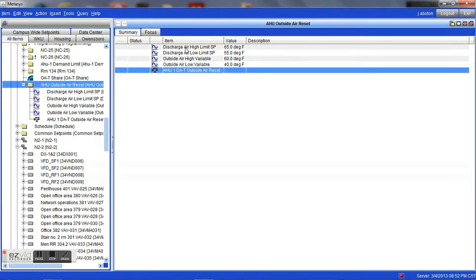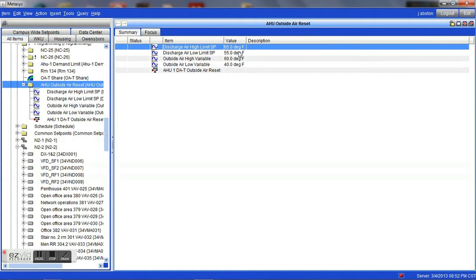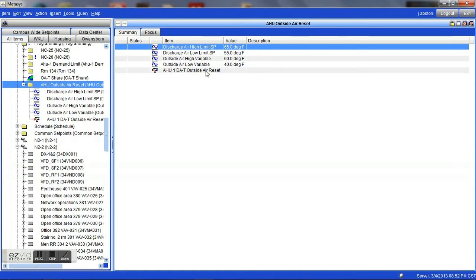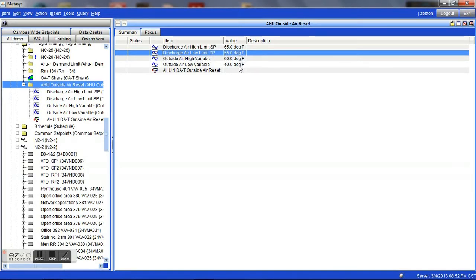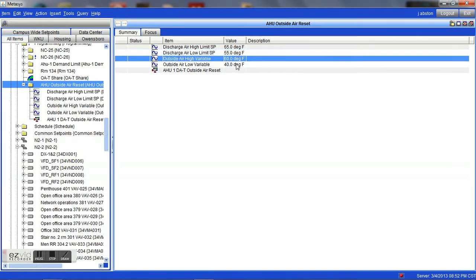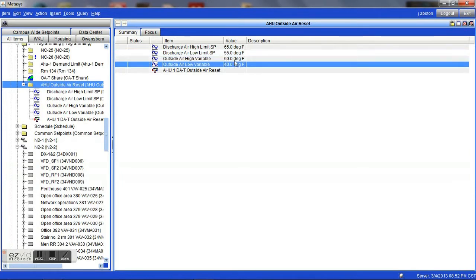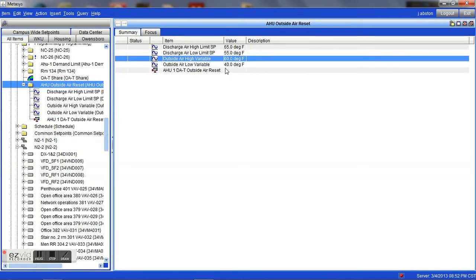One of the elements that we need to create is the discharge air high limit set point. This value is the maximum value that we want to allow the air handler to calculate up to. And, of course, the opposite of that is the low temperature. How low do we want that air handler to discharge based upon outside air temperature? Now, we also have some variables in that as well that can be used and easily adjusted depending on how the building reacts.